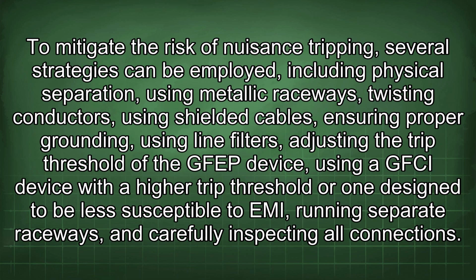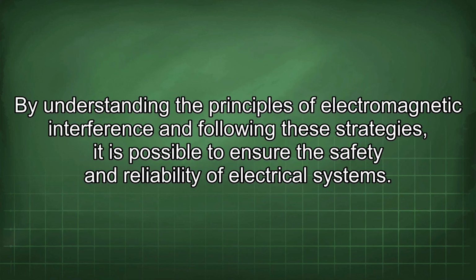To mitigate the risk of nuisance tripping, several strategies can be employed, including physical separation, using metallic raceways, twisting conductors, using shielded cables, ensuring proper grounding, using line filters, adjusting the trip threshold of the GFEP device, using a GFCI device with a high trip threshold or one designed to be less susceptible to EMI, running separate raceways, and carefully inspecting all connections. By understanding the principles of electromagnetic interference and following these strategies, it is possible to ensure the safety and reliability of electrical systems.